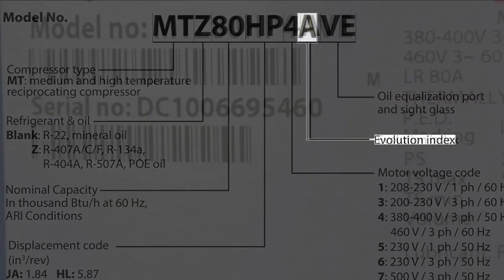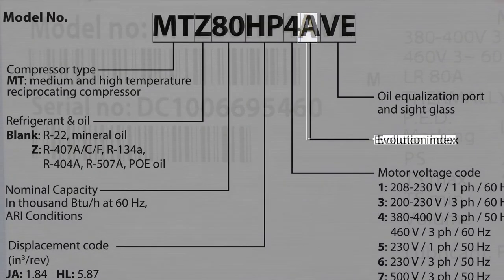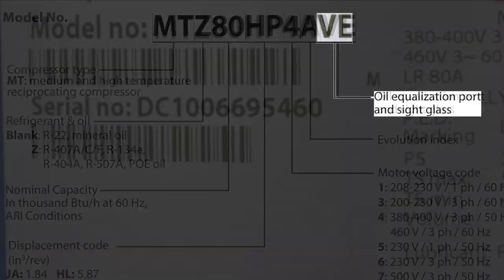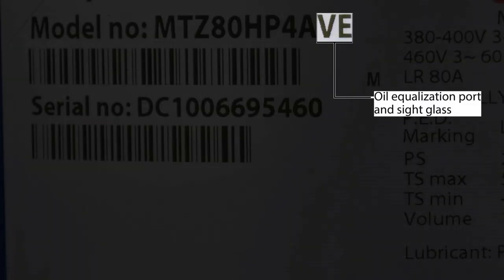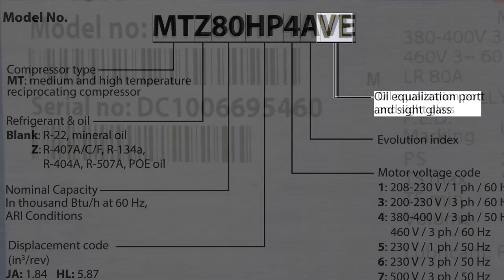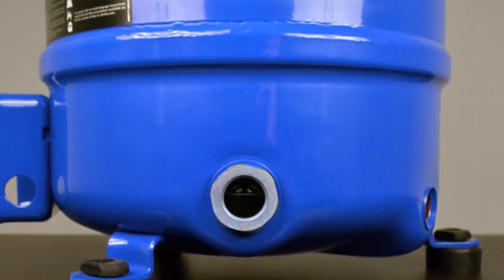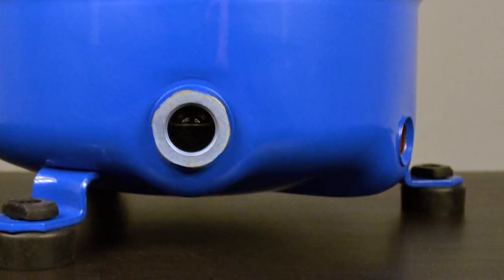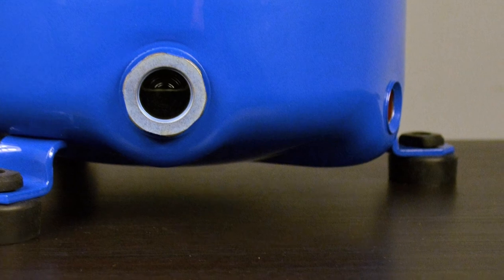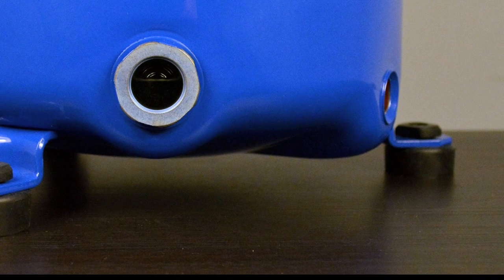The tenth digit signifies the evolution index. The first evolution can either be blank or the letter A. The last two digits of the model number signify the version index, though MT-MTZ compressors only have one version, VE, which specifies an oil equalization port and sight glass. In addition, all MT-MTZ compressors have rotolock fittings.